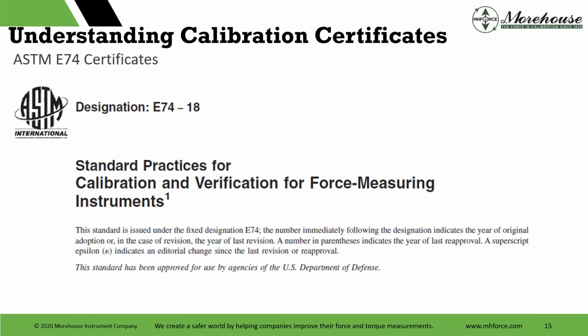So you take this, you start talking about traceability, we're traceable to SI, not NIST, and now we start looking at ASTM, which is ASTM E74, which people here must have interest in, which is the standard practice for calibration and verification of force measuring instruments. So the wording there is interesting. Sometimes I'll use force measuring devices. Sometimes we'll call it a force proving instrument. ISO 376 calls it a force proving instrument. This one calls it a force measuring instrument. A lot of it is the same here. We all know we're talking about force transducers, load cells, proving rings, anything that can measure force.